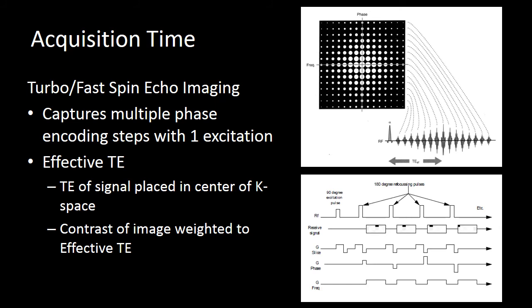Another way to reduce acquisition time is with turbo or fast spin echo imaging. This allows us to generate multiple echoes with one RF excitation. Instead of waiting the full TR between each individual echo, we generate multiple echoes from one RF pulse and fill multiple lines of k-space. We generate an RF pulse, apply a phase-encoded gradient, generate an echo, and fill a line of k-space. We then do a 180-degree refocusing pulse, another phase-encoded gradient, and generate another echo to fill another line of k-space. With modern techniques like turbo spin echo, we can sometimes fill all of k-space for a single slice with a single acquisition.